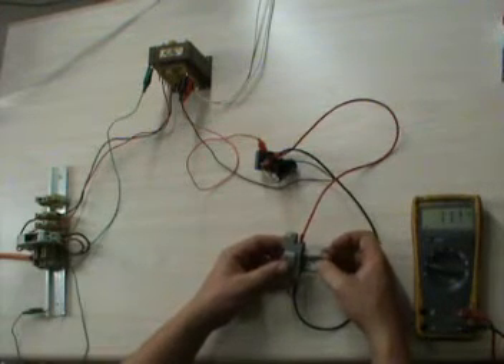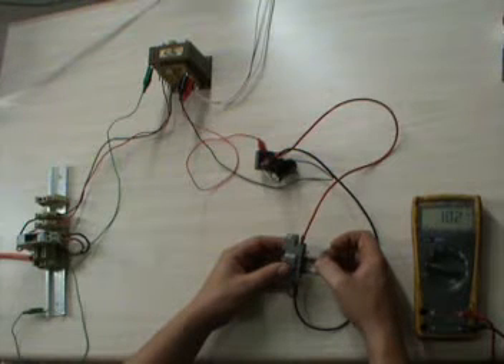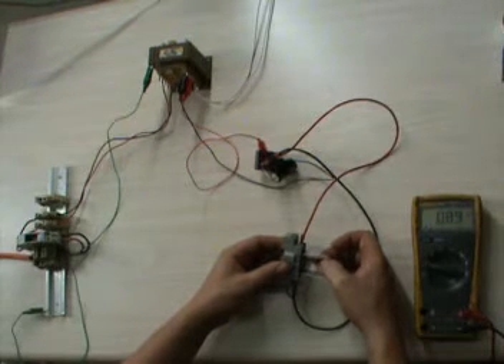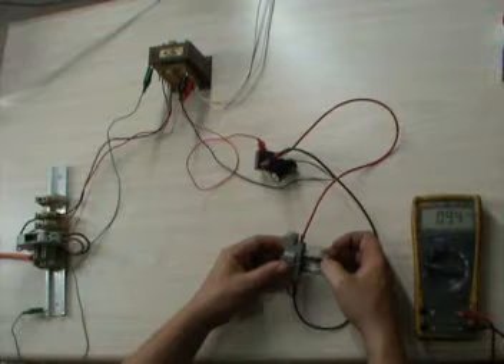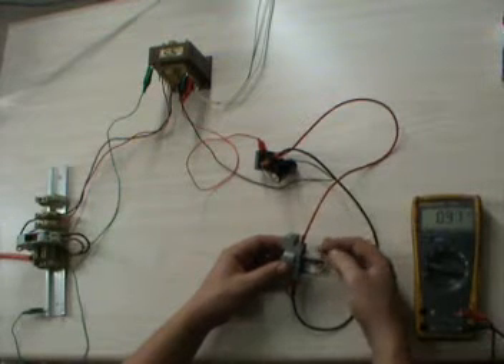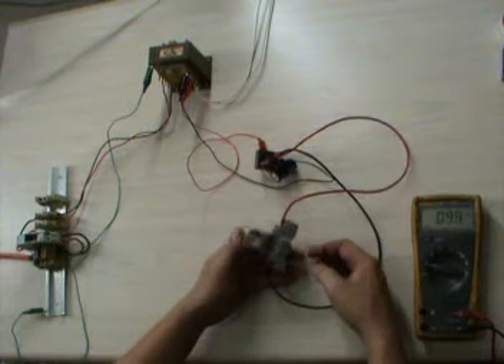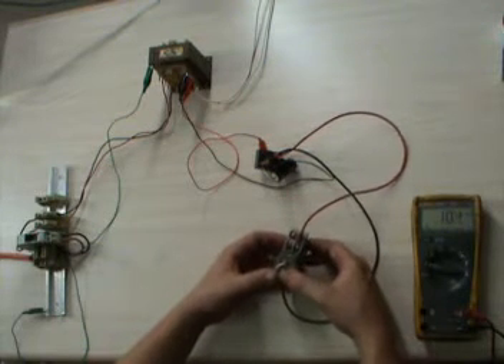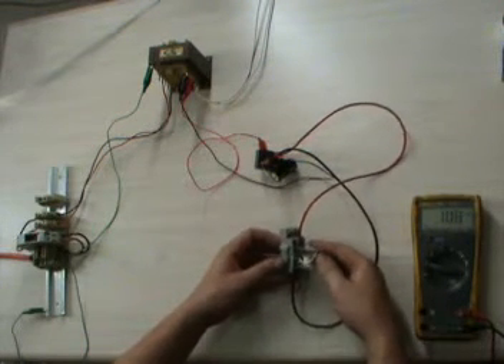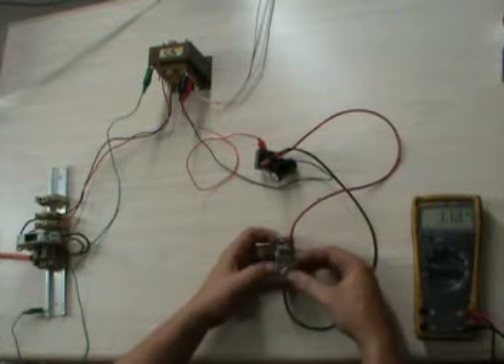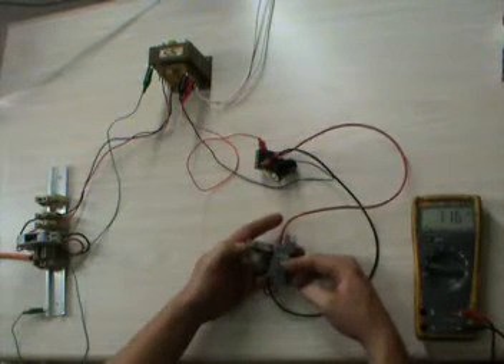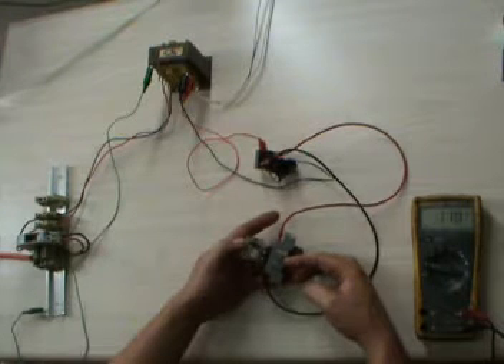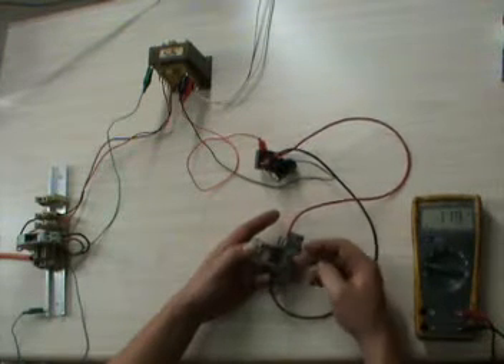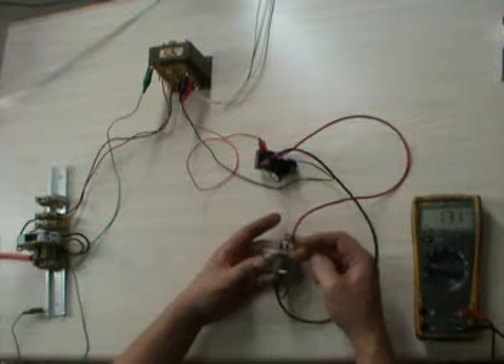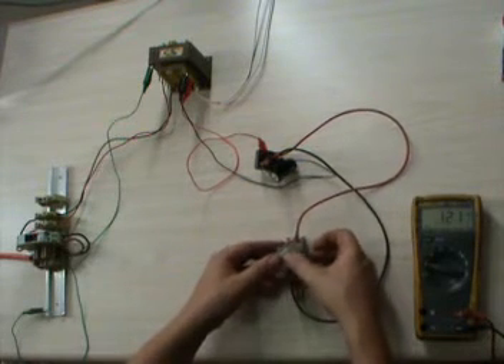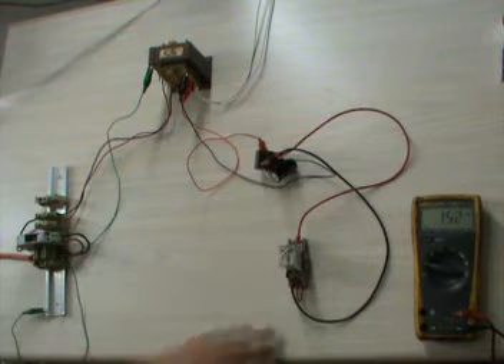Now with this nice blue arc in between the two contact points, the arcing is going to pit, dirty up and carbonise the contacts. So this setup for this relay is not very good for long-term efficiency. These two contacts will start to increase in resistance over a period of time, and they will get to the point where the voltage drop across those two contacts will be quite significant, and you'll see your project starting to fail.